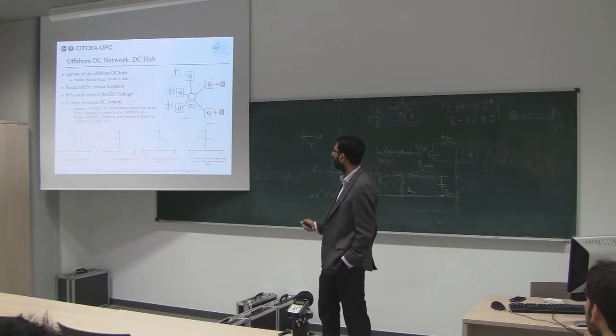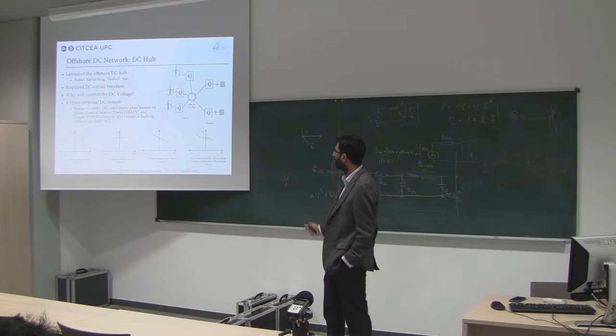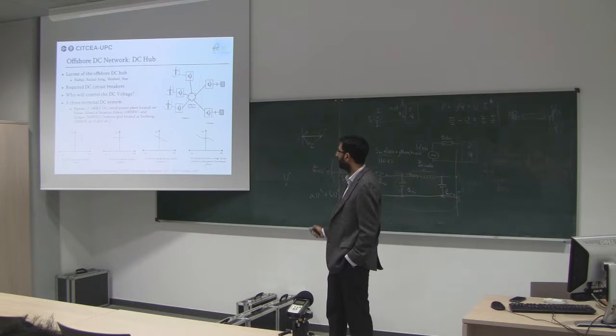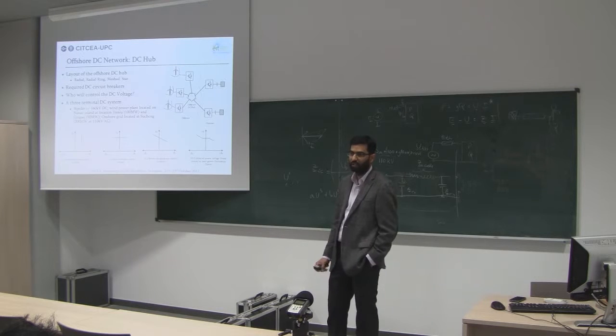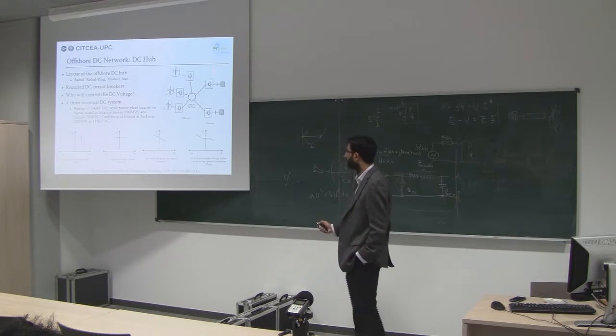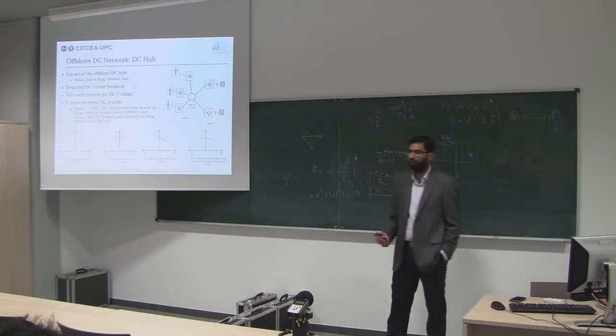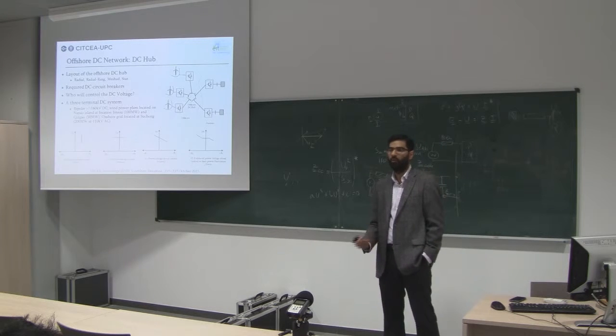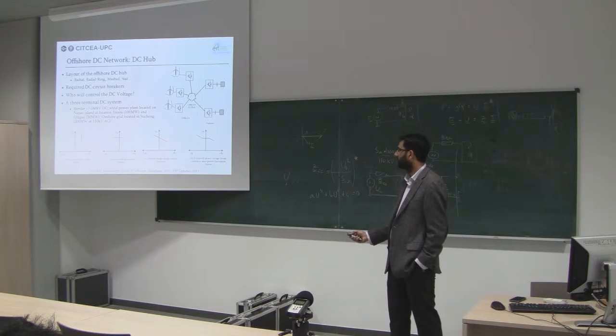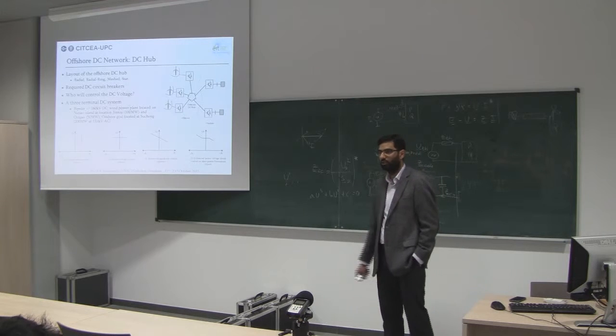The converters on the onshore side have droop characteristics and both work as slack sources in the DC network. But the problem is you will have a fluctuating power flow because the wind power changes and your power is changing accordingly. So one concept is to have a limit: at a particular power infeed you have a constant DC voltage, and after that the slave can control the DC voltage as well.